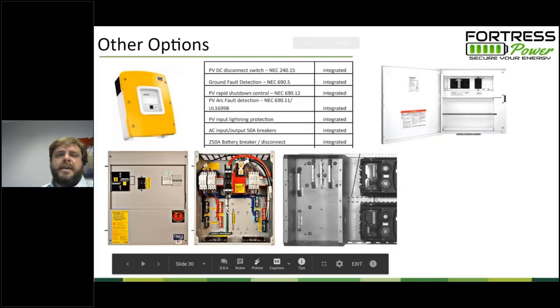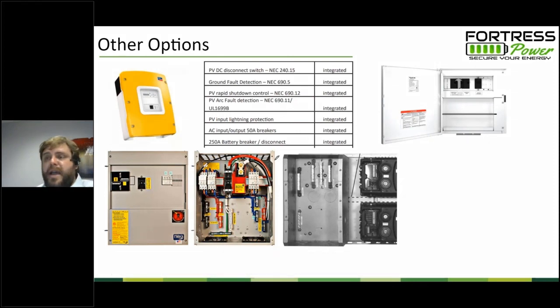Still a very rare circumstance, and so many installers will just go ahead and skip over that step. The last option is to buy these battery combiner boxes. Midnight has developed one, Outback has developed one. But looking inside the box, we can see they're buying these insulated bus bars to be stood up off the box, and I can buy a power distribution block instead. And they're using breakers, which are really nice to have for that on-off. This might actually be a touch-safe fuse holder instead. And so you can put your own insulated fuse blocks and terminal blocks into a metal box and save a little bit of money compared to the nice, manufacturer-provided package solution.